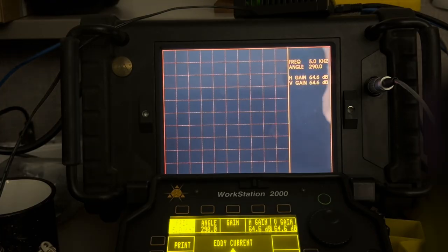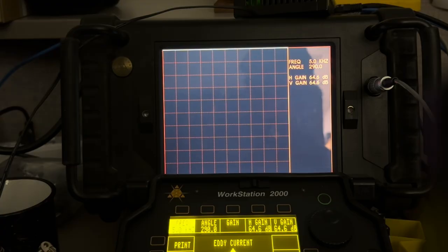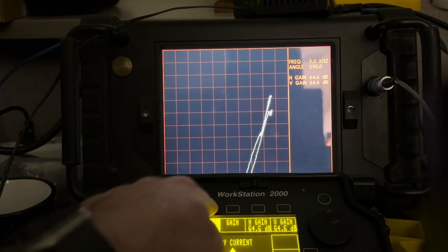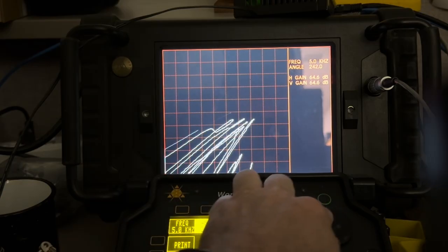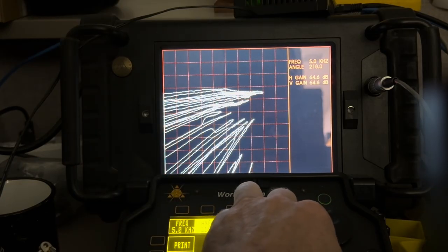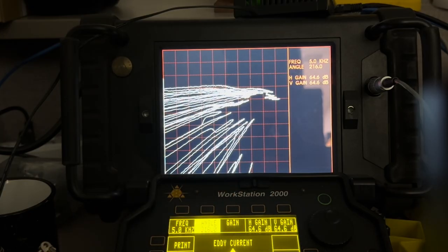All right. This says 1 to 50 kilohertz. So this coil is designed to operate in that low test frequency range. So now I've got 5 kilohertz. And we're going to have to set our noise because it's going to be way out of whack. Okay, tapping on the part just like you do at the dentist. When you put a filling in, it's tap, tap, tap.